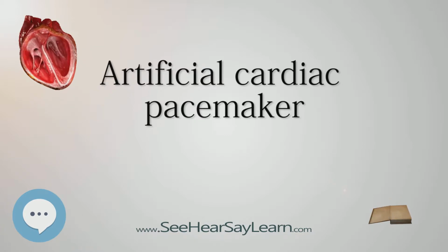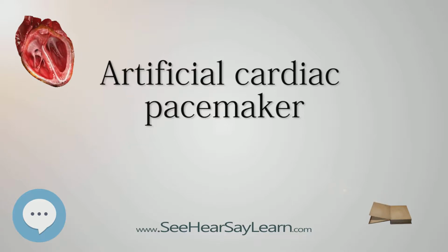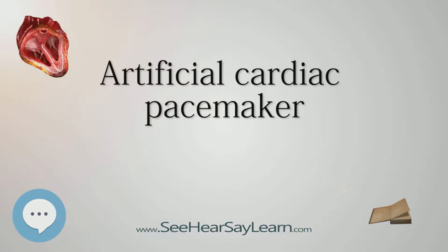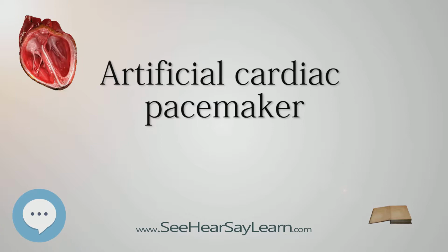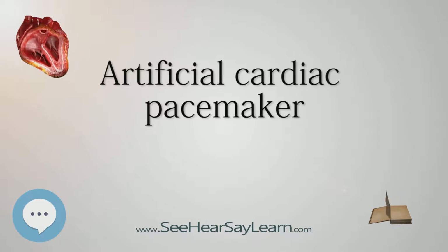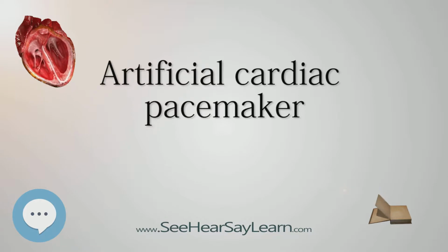Where the problem is atrioventricular block, AVB, the pacemaker is required to detect, sense, the atrial beat and after a normal delay, 0.1 to 0.2 seconds, trigger a ventricular beat, unless it has already happened. This is VDD mode and can be achieved with a single pacing lead with electrodes in the right atrium, to sense, and ventricle, to sense and pace. These modes, AAIR and VDD, are unusual in the US but widely used in Latin America and Europe.